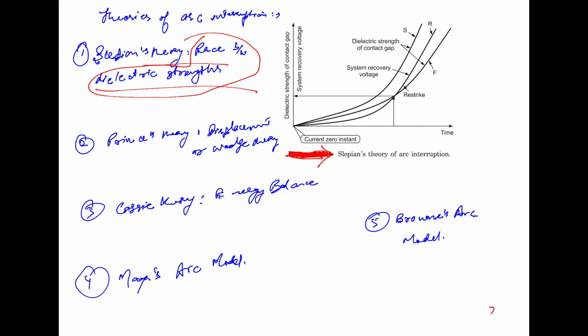So, this is also depicted in this figure. From this figure, you will observe that the curve marked R represents the way in which the system recovery voltage rises after the current zero. Two instances of the rise of dielectric strength of the contact gap are shown in the curves marked S. The dielectric strength rises at such a rate that it is always greater than the system recovery voltage, that is R. Hence, the dielectric strength of the contact gap wins the race, making the interruption successful.